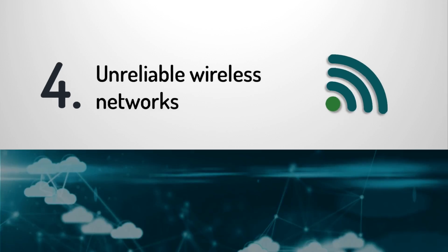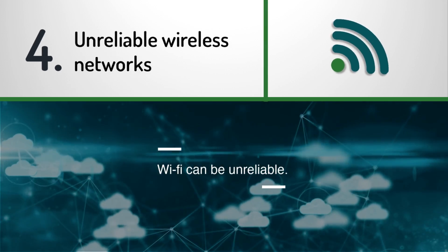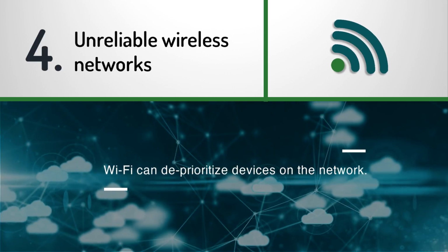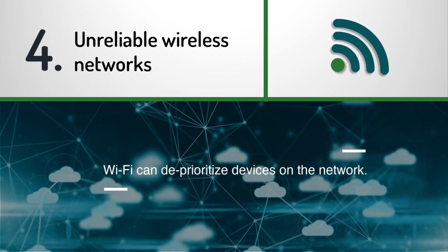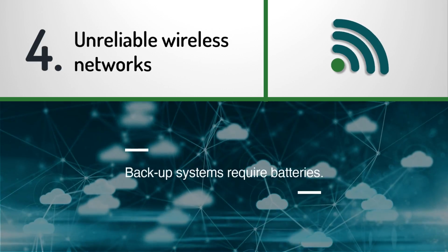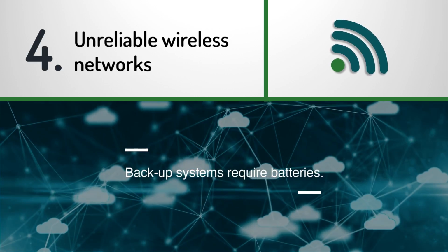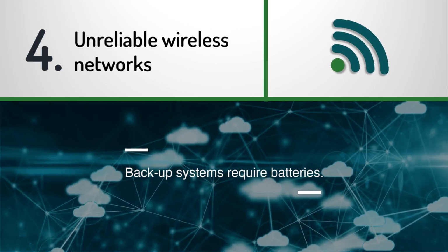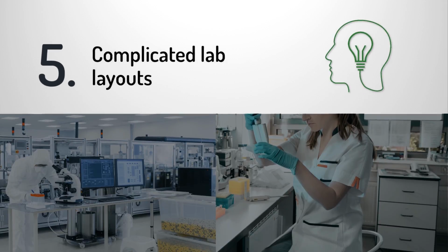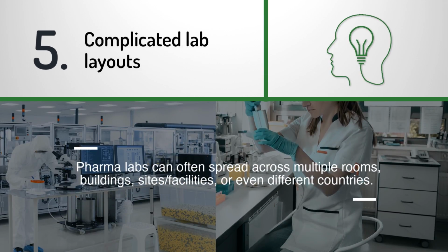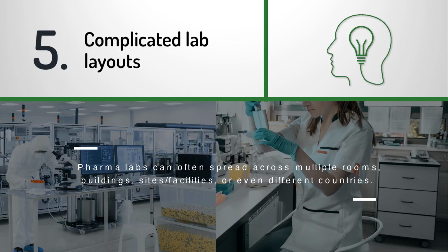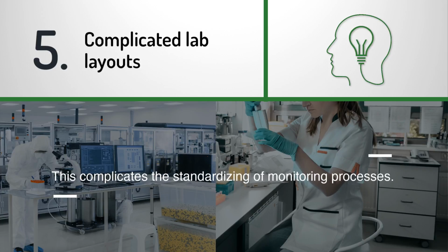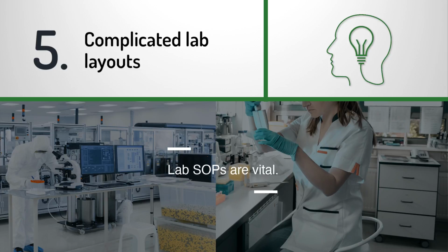Unreliable wireless networks. Certain Wi-Fi networks can be unreliable depending on infrastructure. They can deprioritize devices on the network, kicking devices off the network and causing false alarms. Backup systems also require batteries that need to be changed. With the wrong system, spotty connections can result in data loss. Complicated lab layouts. Pharma labs can often spread across multiple rooms, buildings, sites, or even different countries. This complicates the standardizing of monitoring processes. Without tight adherence to SOPs across all sites, pharma organizations are subject to errors, losses, and failures.